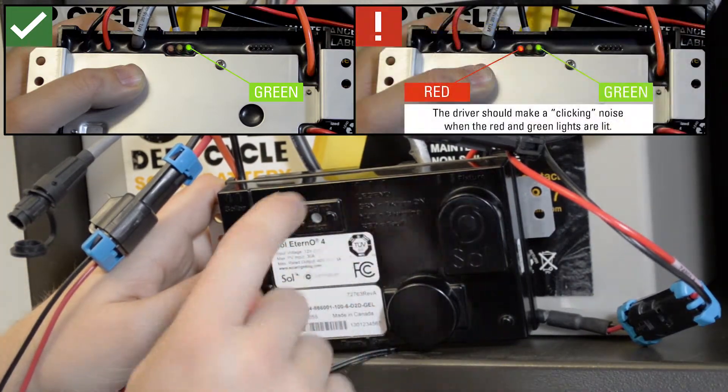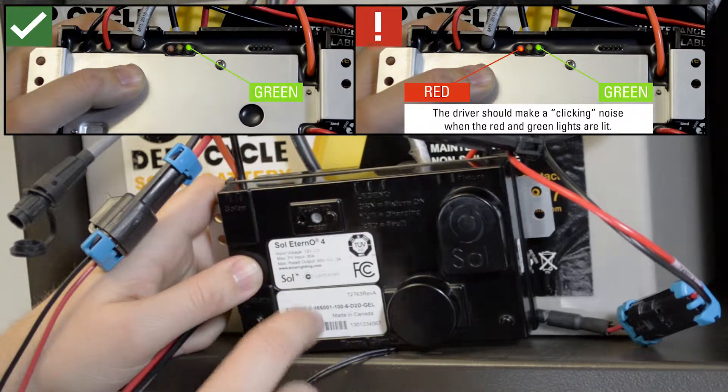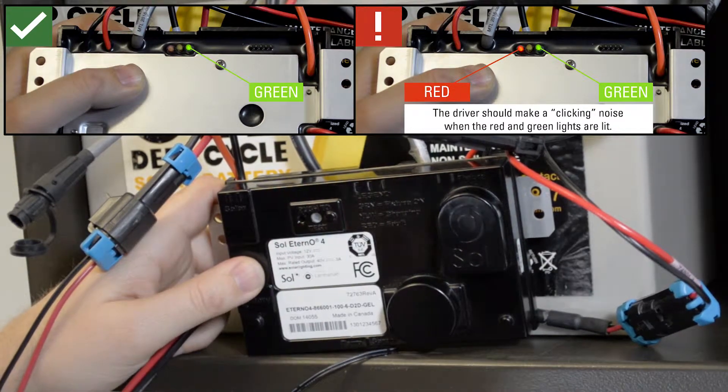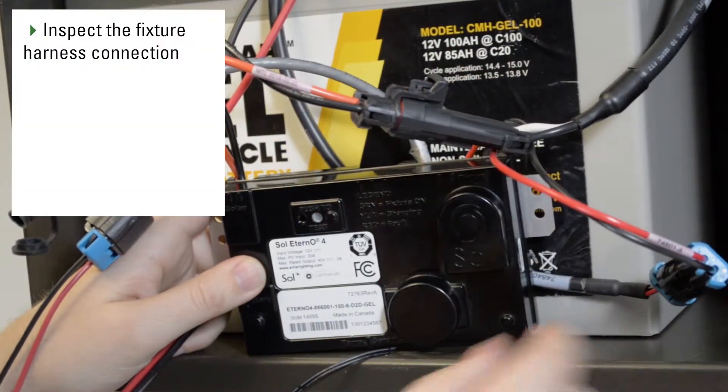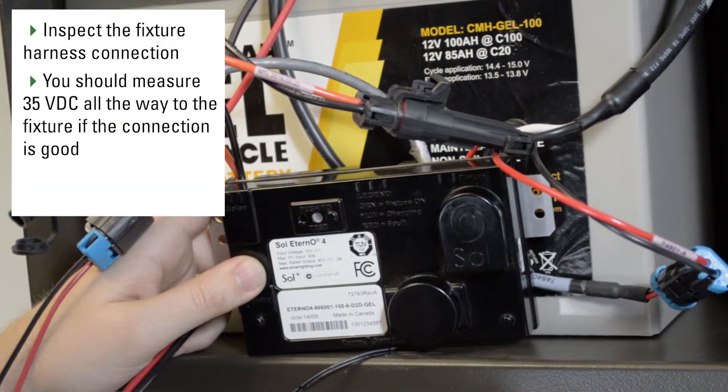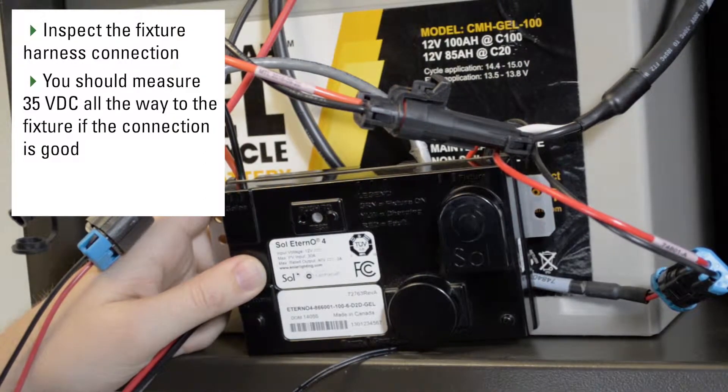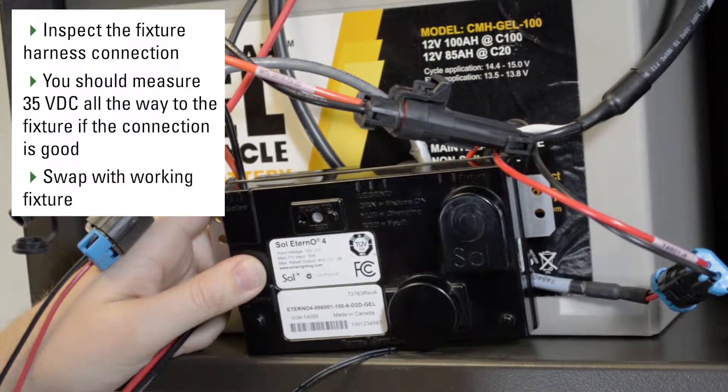If it doesn't, you'll have a green and red solid indicator light and that means there's either a poor connection or you have an issue with the fixture. Trace connectivity using the fixture harness to the fixture, or if you have another fixture on site that you know is good, test to make sure that the fixture is operational.